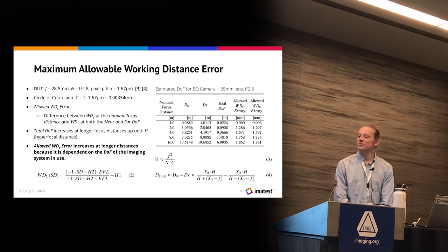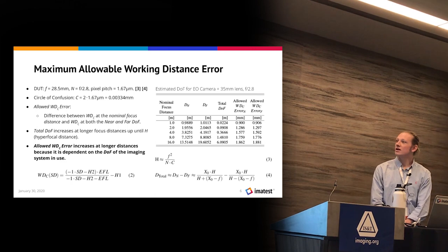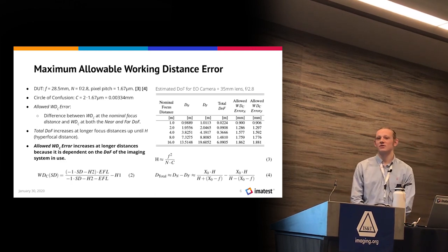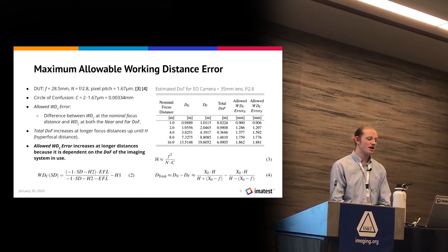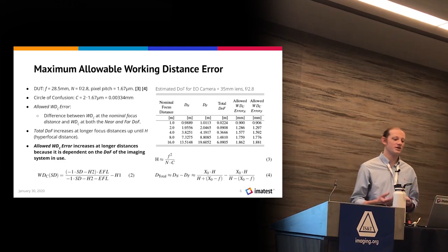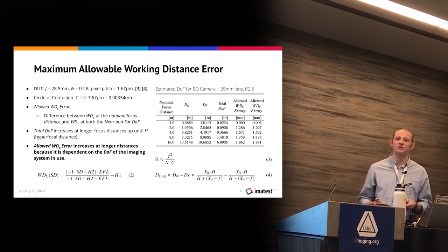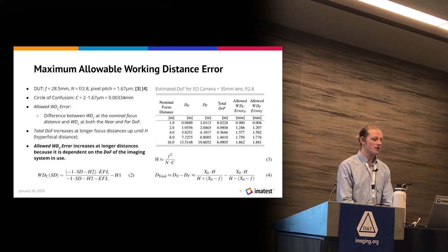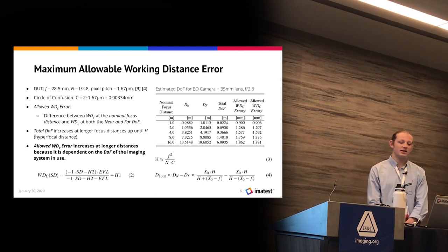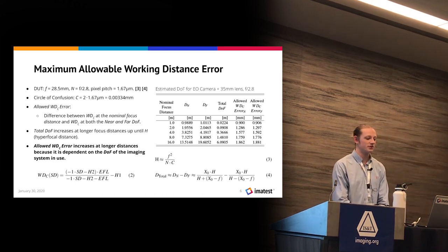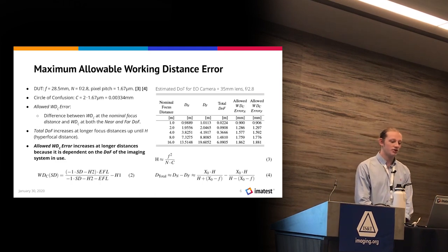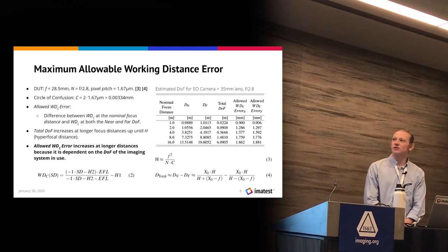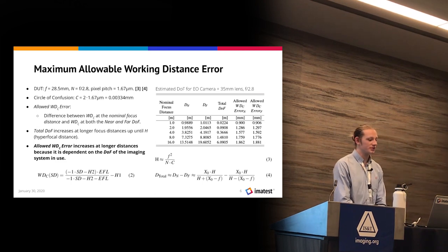For our testing, we chose a machine vision camera with a half-inch sensor and 10.5 megapixels. It's extremely important to perform this test with a lens that has a lockable focus, as we want the focus distance to be consistent between the real world and the simulated distance image captures. We chose a camera lens with a relatively narrow field of view. The field of view that we're using is about 10.4 degrees. We also achieved a narrow depth of field with the aperture at f/2.8 in order to push the limits of the collimator fixture system.